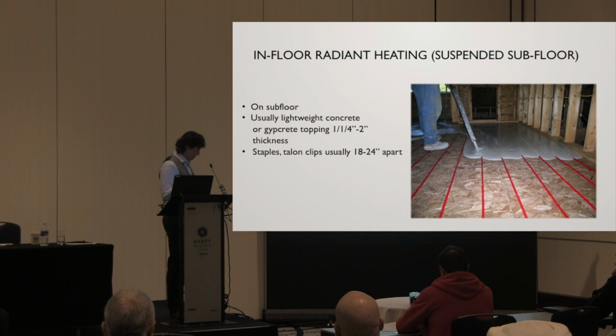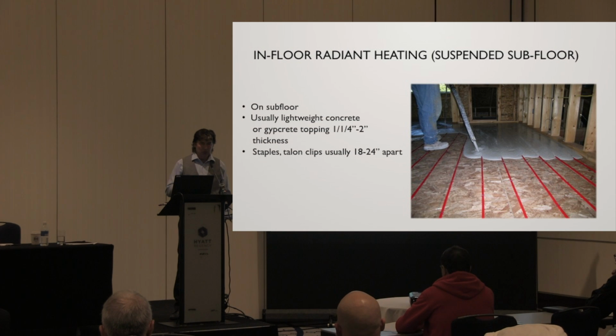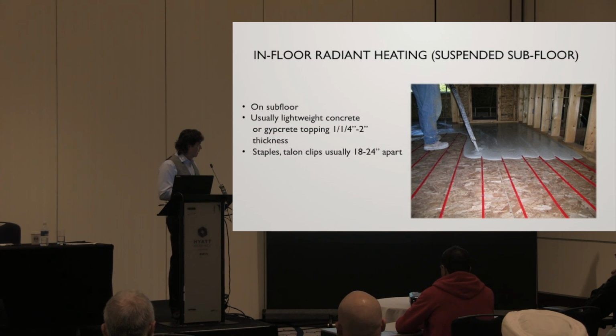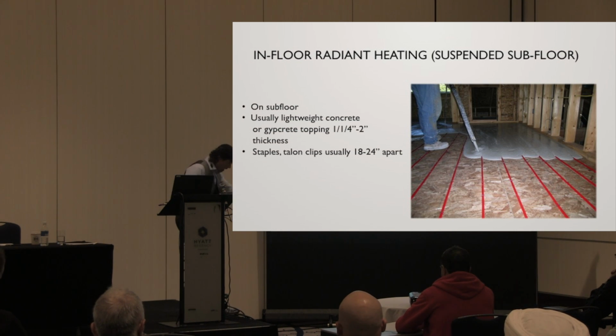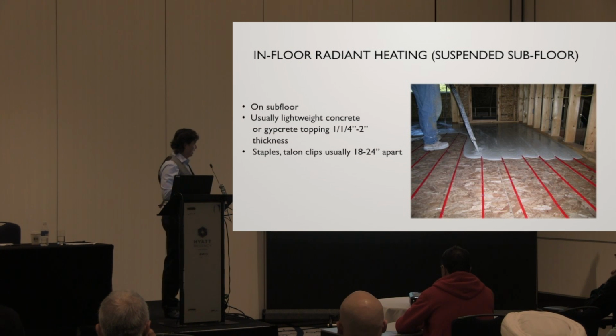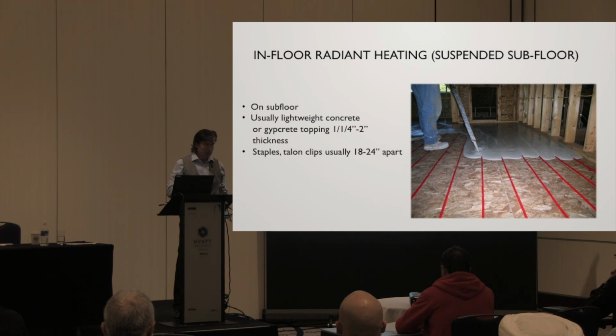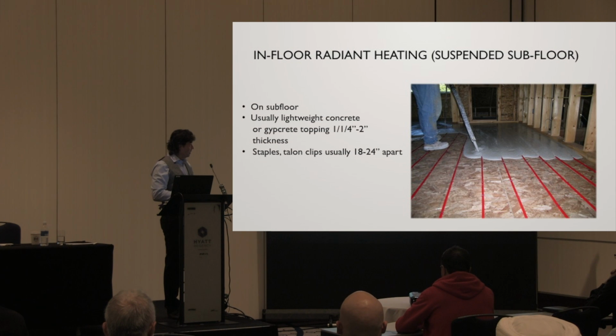Now, when we're talking about testing, let's just go back here. So these staples, how many people have seen contractors use staple guns to staple down radiant? Okay, well, that's actually a fairly common way to put your radiant tube down, with staples. With a pneumatic stapler, you go along, it's great, fast, quick, kapow, kapow, kapow, and down it goes. The problem is you can miss. These get mighty close, and I can tell you that the percentage of staples that actually go through the radiant tube is pretty high. And I can also tell you that if you throw 45 psi into that pressure test, that staple could probably take that. You won't even know because it's into plastic tube, into PEX pipe.